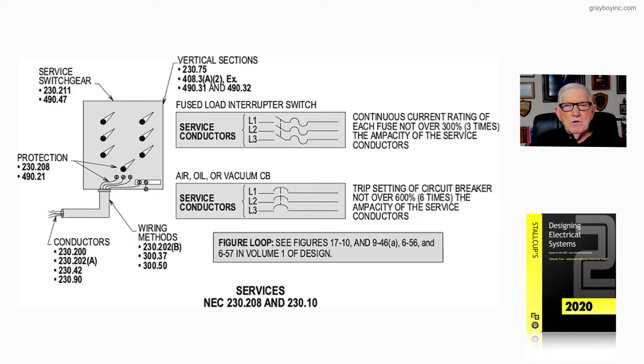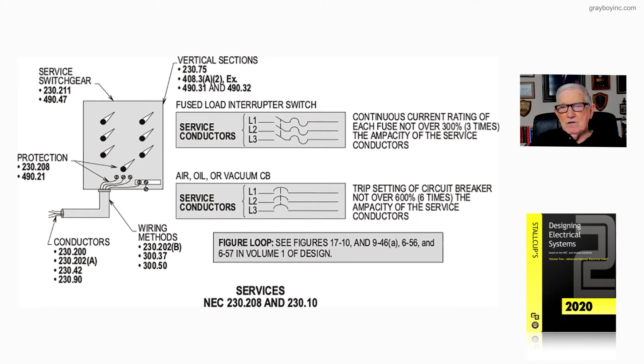For your air, oil, or vacuum-type circuit breaker, with L1 and L2 hitting the breaker, trip settings shall not exceed 600% the ampacity of the service conductors. For more information in the NEC loop, we suggest you see figures 17-10, 9-46(a), 6-56, and 6-57 in volume 1 of design — and figure 17-10 would be in volume 2 of design.